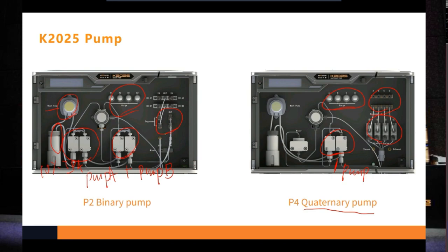I'll take the binary pump as an example of how the solvents flow through the pump. The solvents come from the solvent bottles on the top, so the mobile phase should be here. It comes to the selection valve and the degasser for the degassing, and there are two solvents in a binary pump. One will go to pump A, another one will go to pump B, and they mix for the first time here.